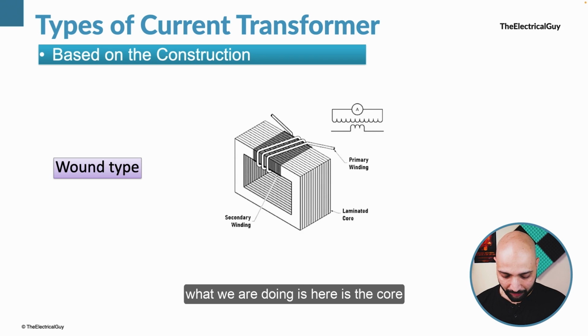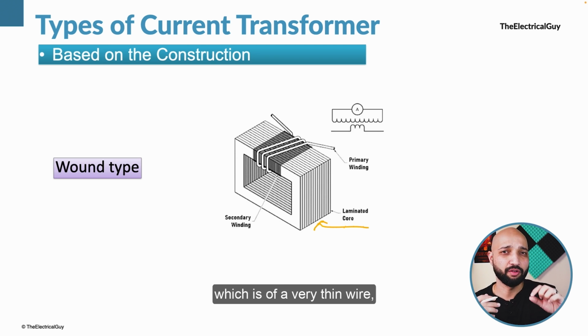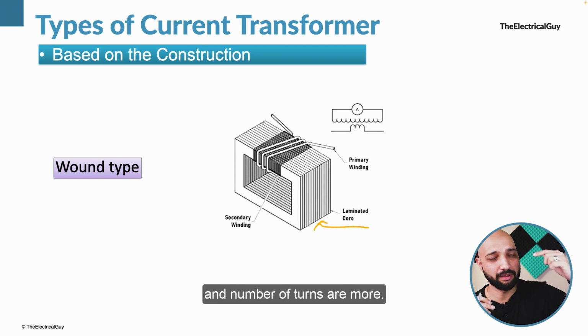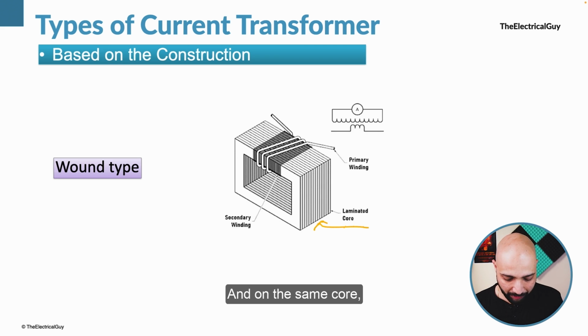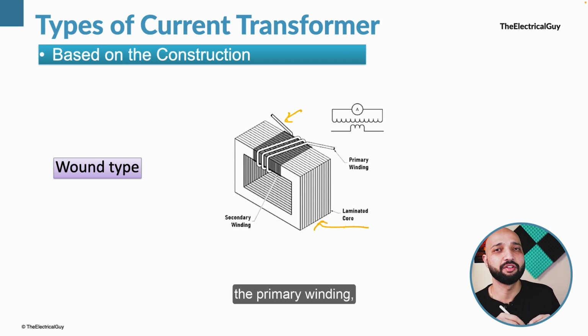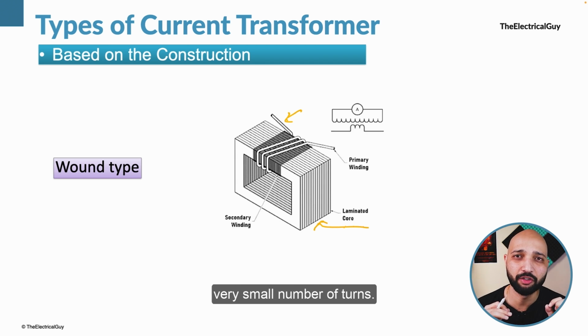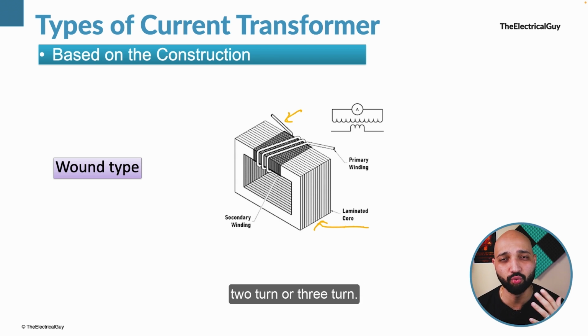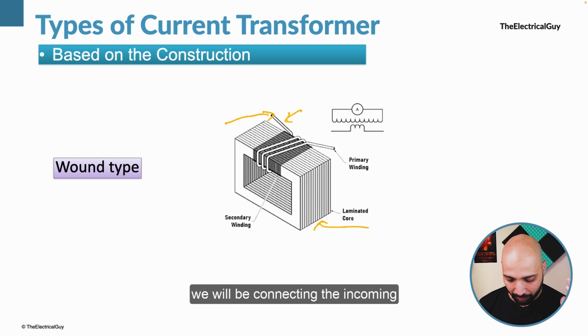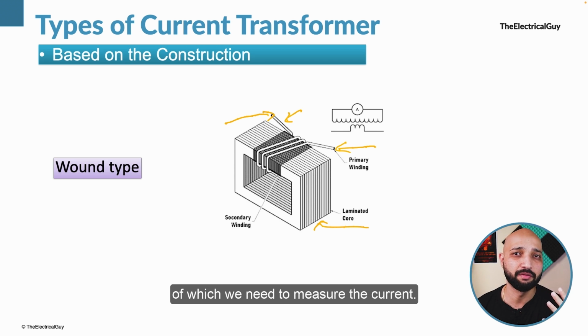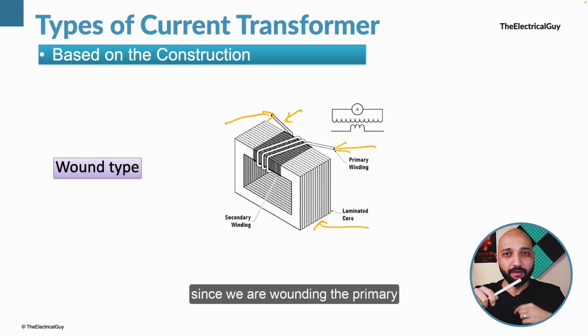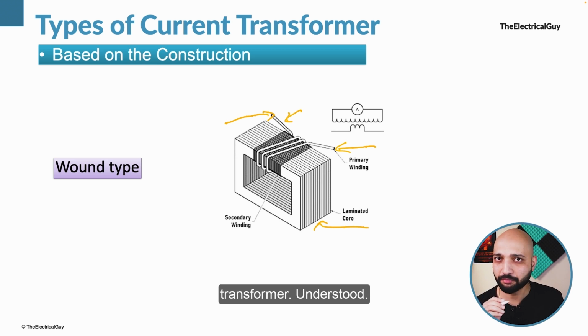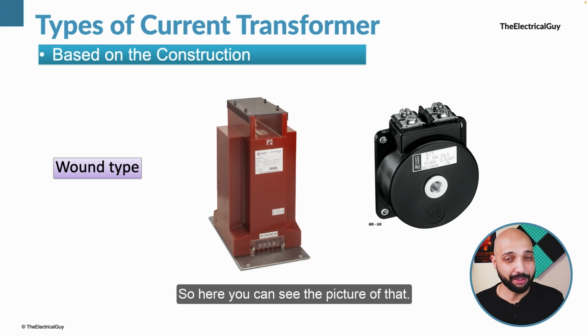Now in this, what we are doing is, here is the core that we have. To this core, we have wound the secondary winding, which is of a very thin wire and number of turns are more. And on the same core, we have also installed the primary winding, which is of a thick wire and a very small number of turns. So it can be single turn, two turn or three turn. So in series with that, we will be connecting the incoming wire or the conductor of which we need to measure the current. Now, since we are wounding the primary on the secondary, this is called as wound type current transformer. Understood? So here you can see the picture of that.